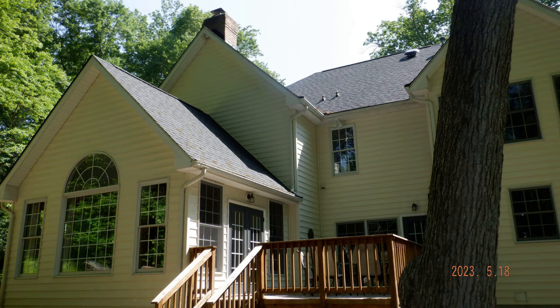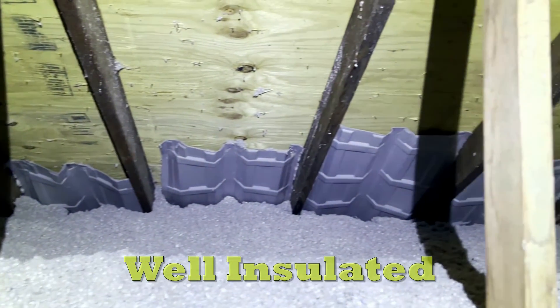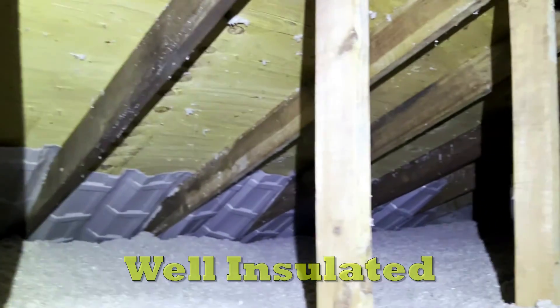Let's talk about the typical boundary locations around a Maryland house. The first and most common is an attic flat — that's your typical flat ceiling wherever the area above the ceiling is connected to the attic. You could have a second-floor attic in a two-story colonial, or an addition on the back with a separate attic. The recommended R-value for a flat attic ceiling in Maryland is R-49.